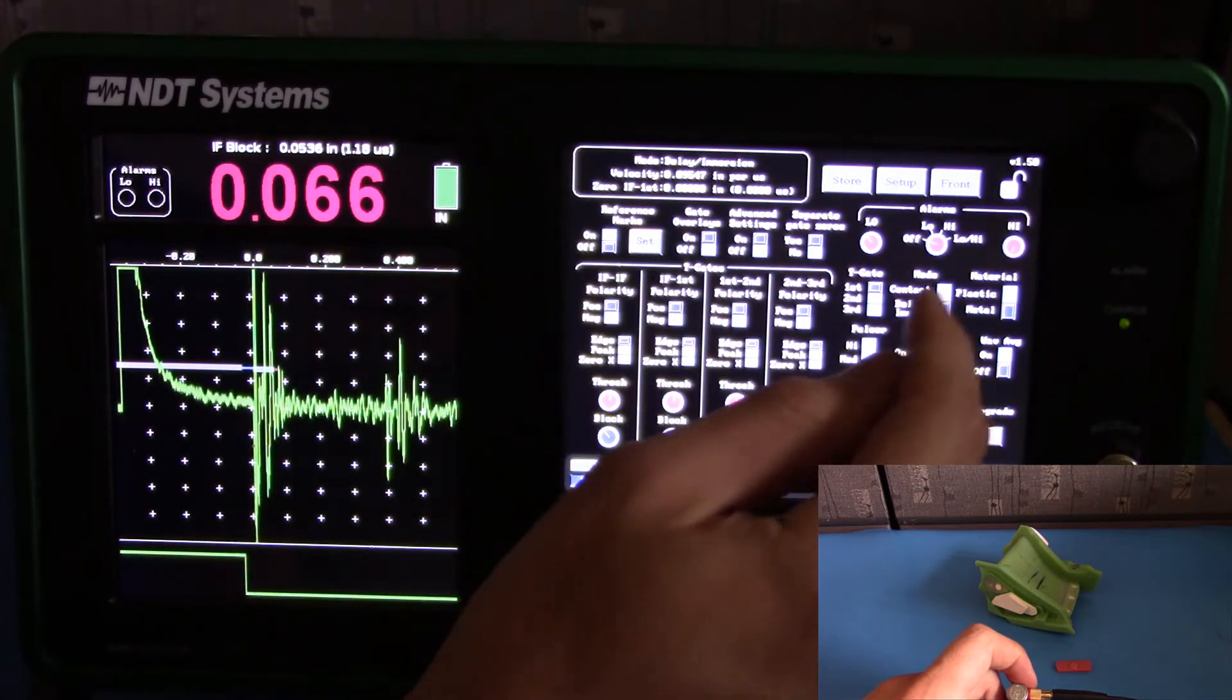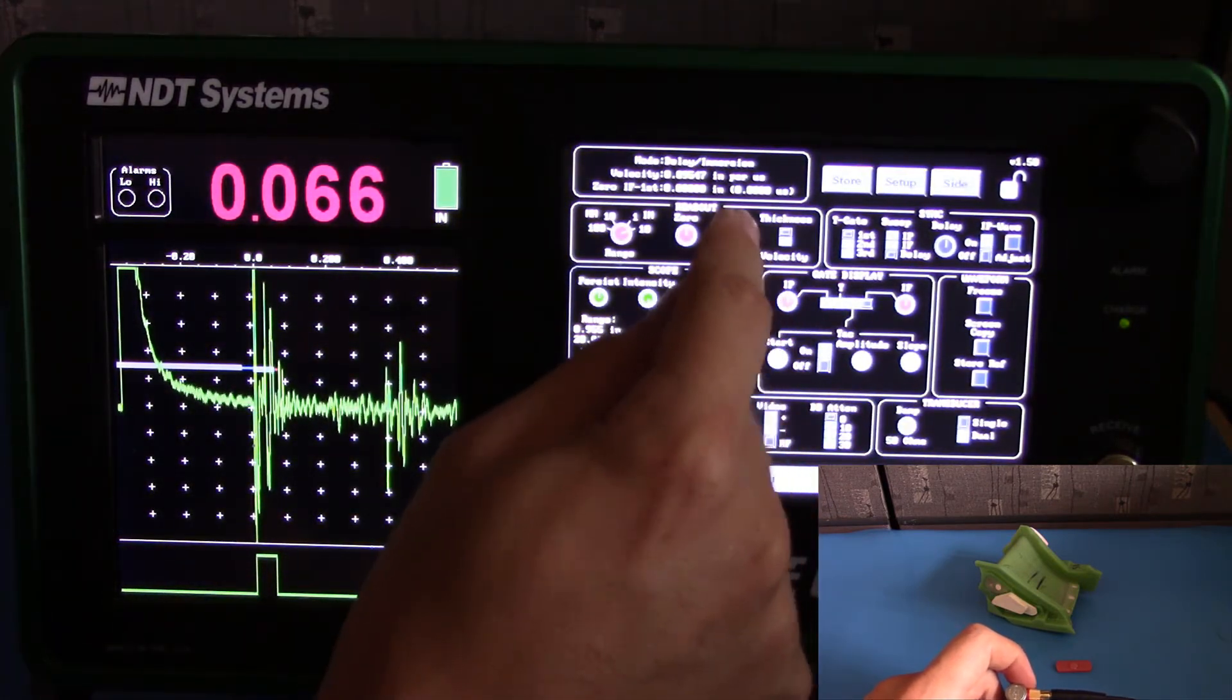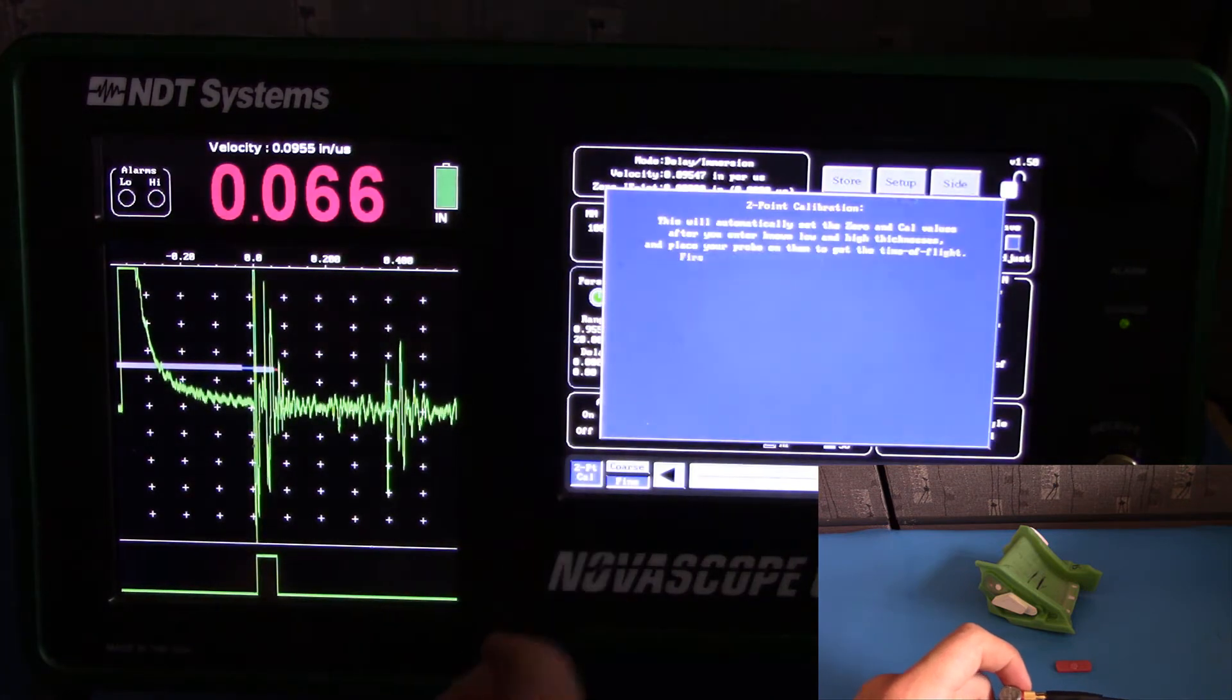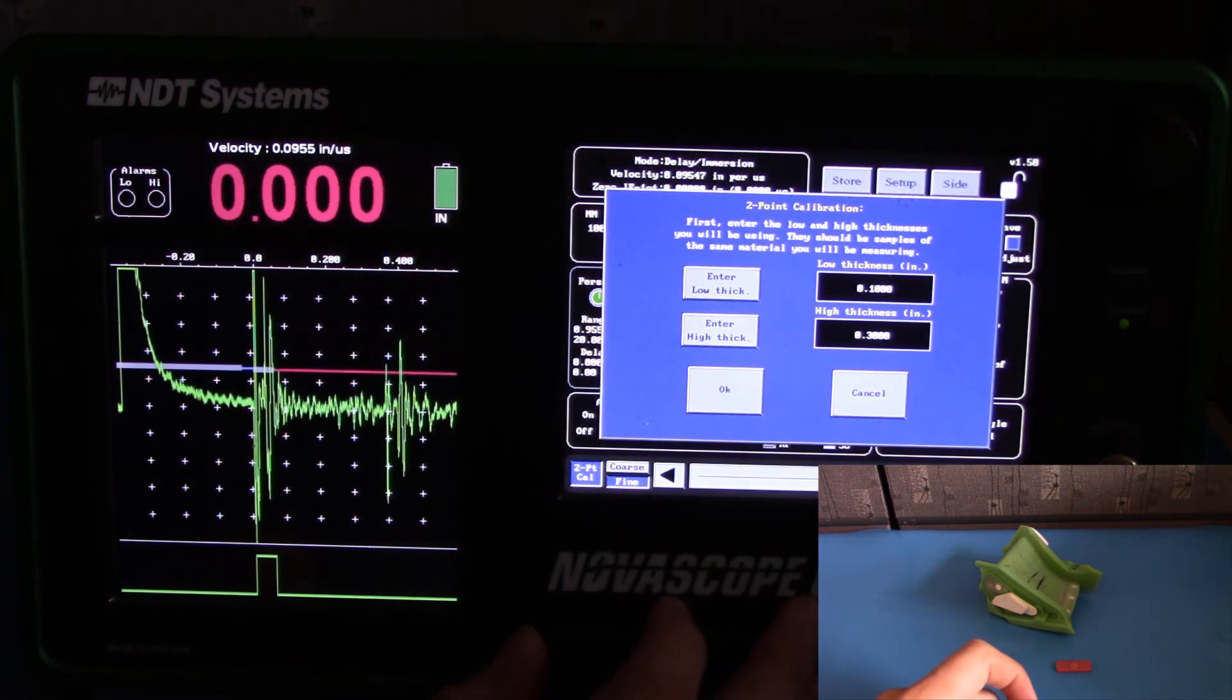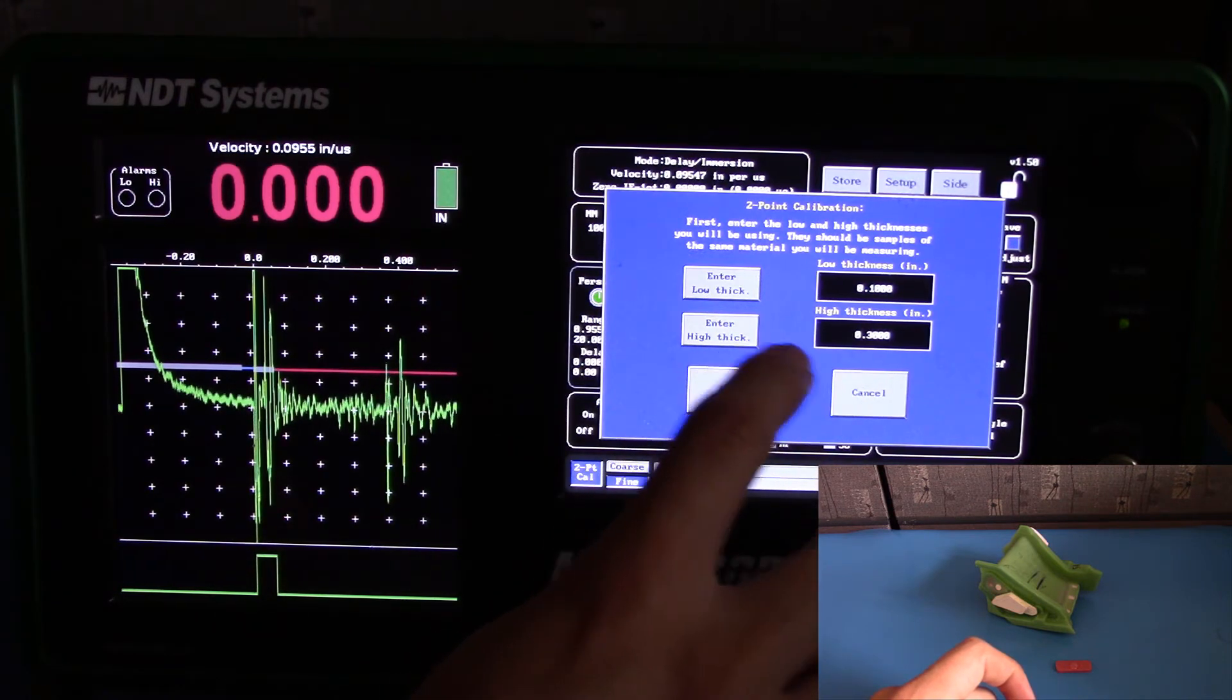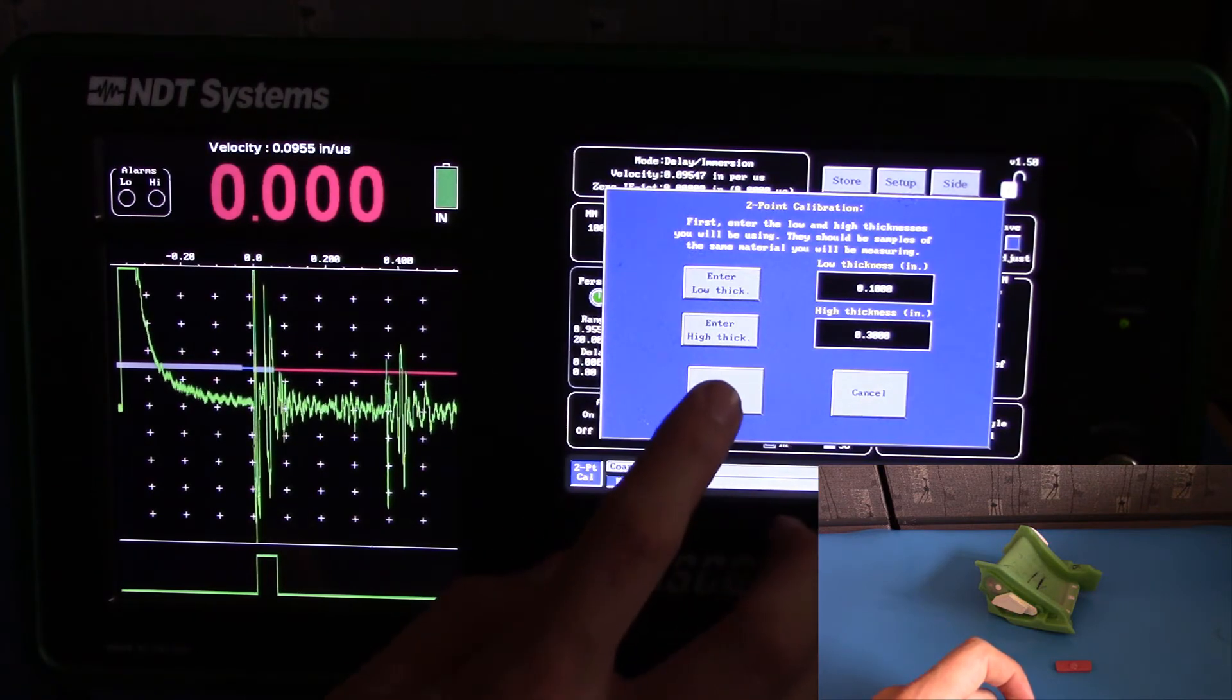Now we're good to couple and calibrate with our 2-point cal. Go to the cal button again and select 2-point cal. Hit OK. Similar as before, but this time, our high thickness is 0.3 inches instead of 1.5. If your settings are correct, hit OK.